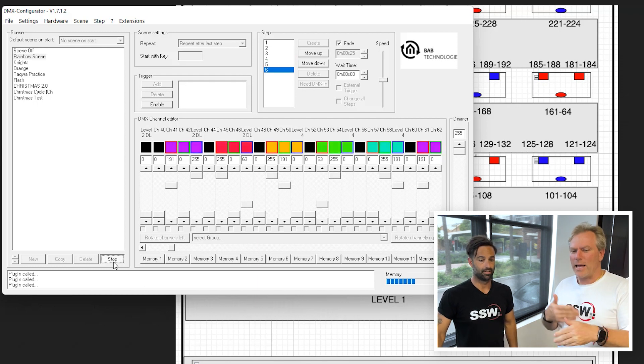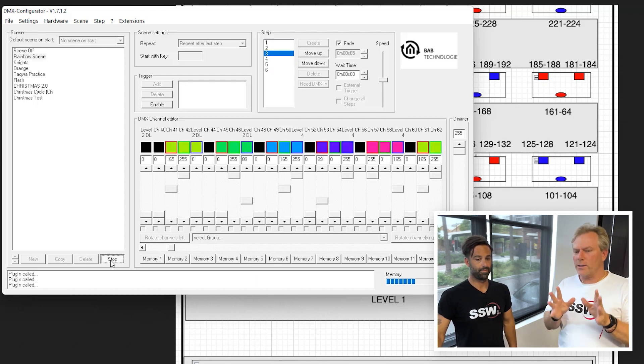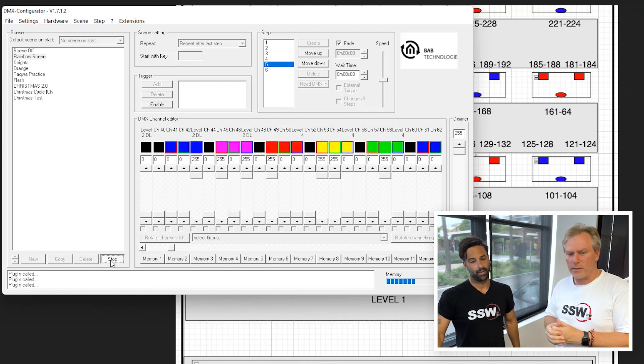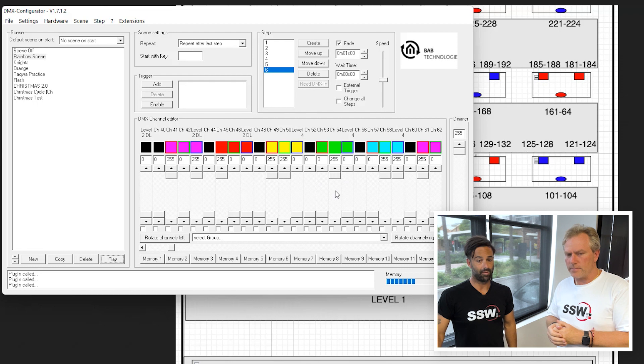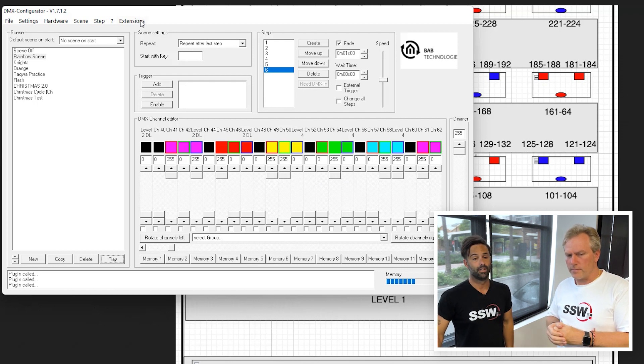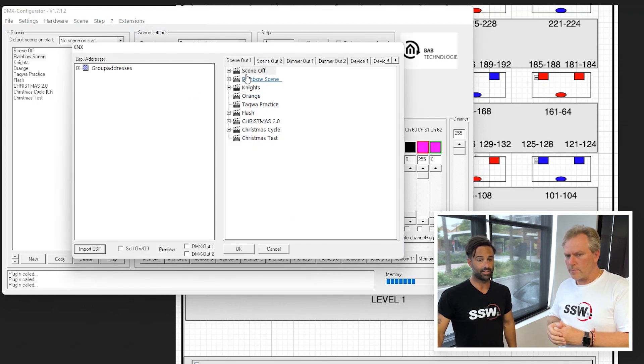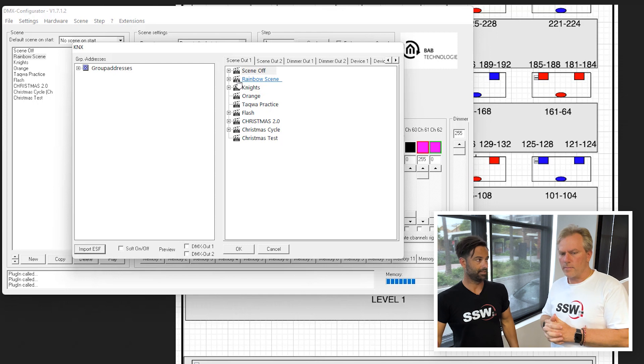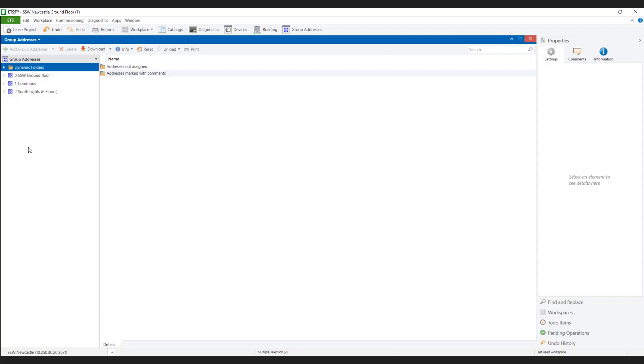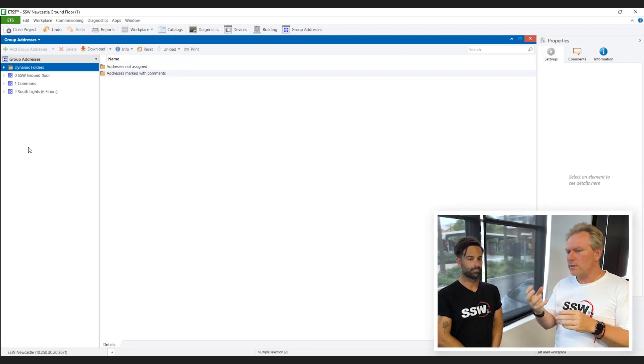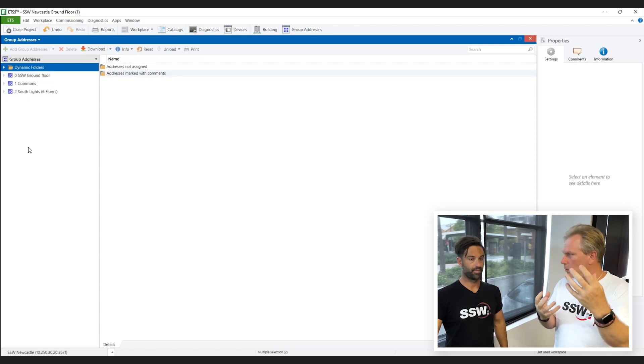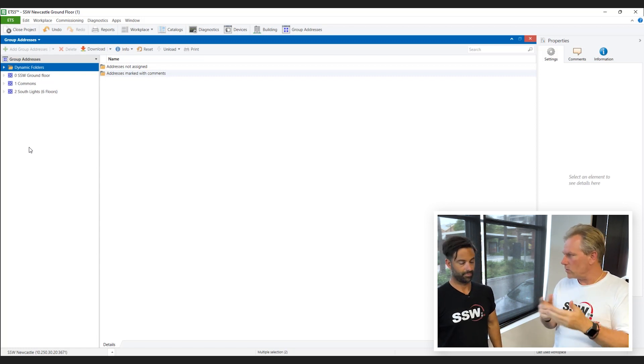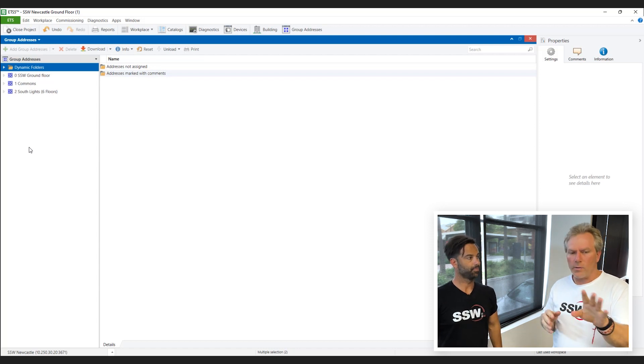So now you've got this nice simulation. What is the next step after you've done this? So the next step, we know that we've got these scenes. We want to check to make sure that the scenes are within our extension. So we go to extensions, we'll check out the internals. We can see here that the scene outs, all our scenes are populated here within this window, which is what we want to see. So after that we need to create an address. Now how we do that is we create it through KNX. Okay so now we've got the ETS configurator. This is the thing that talks to the physical hardware brain.